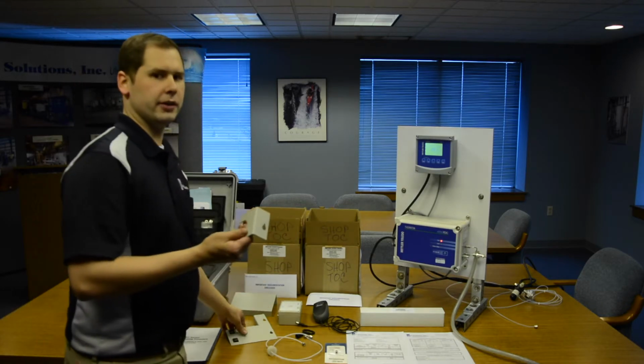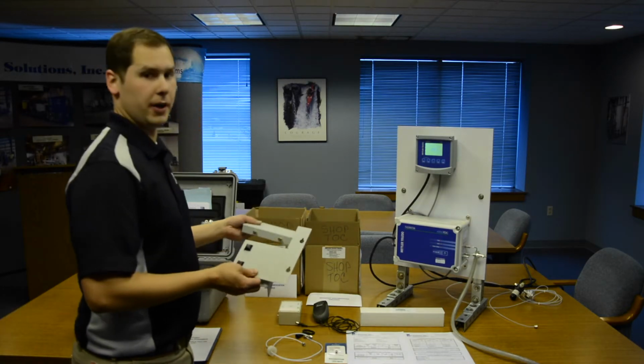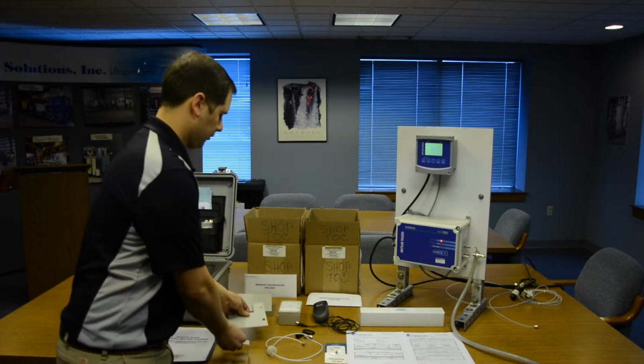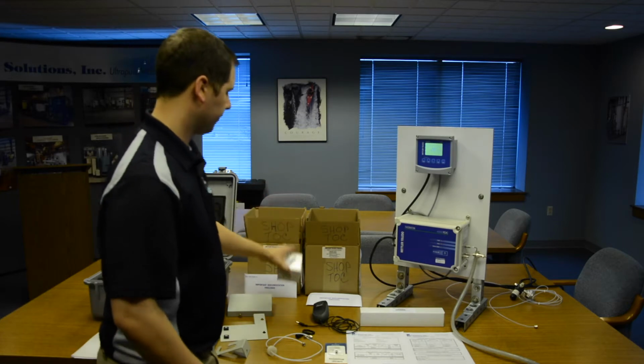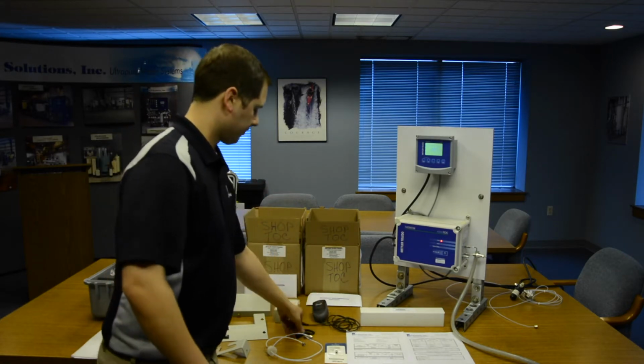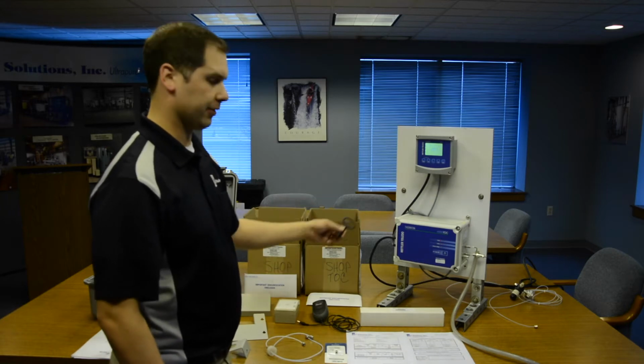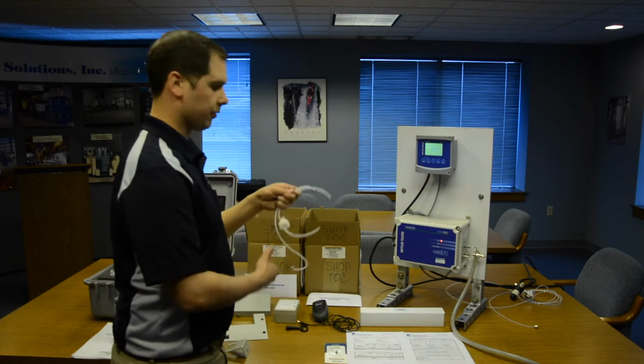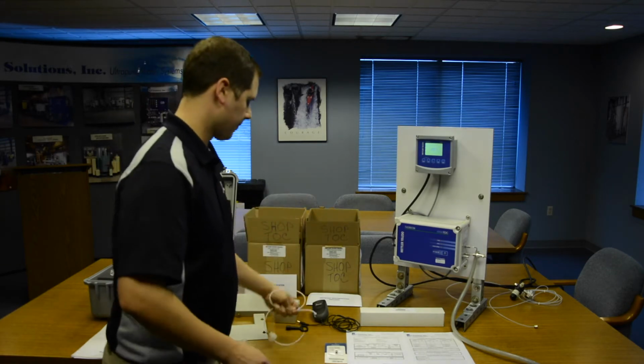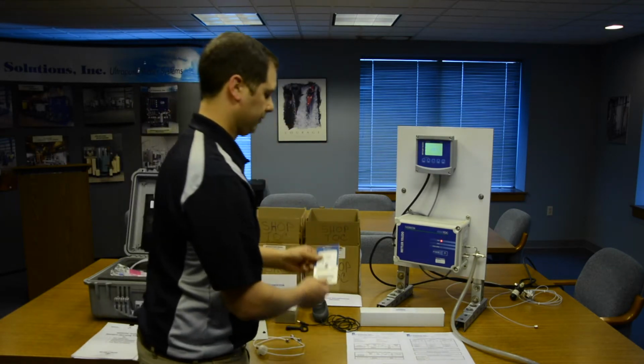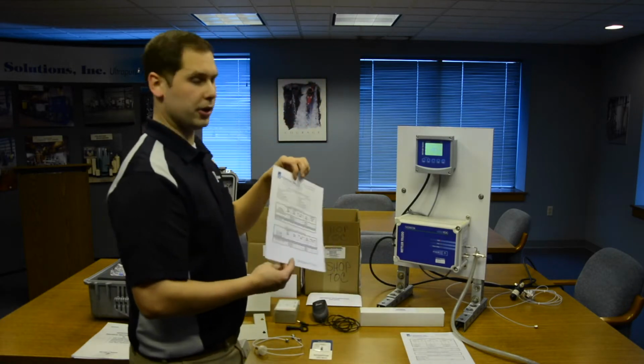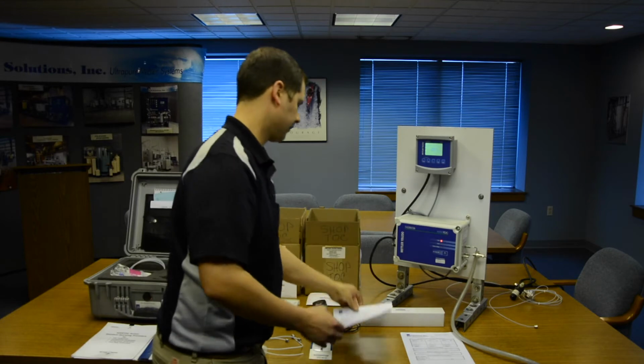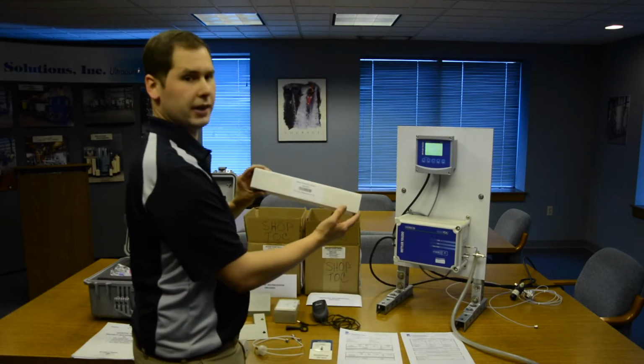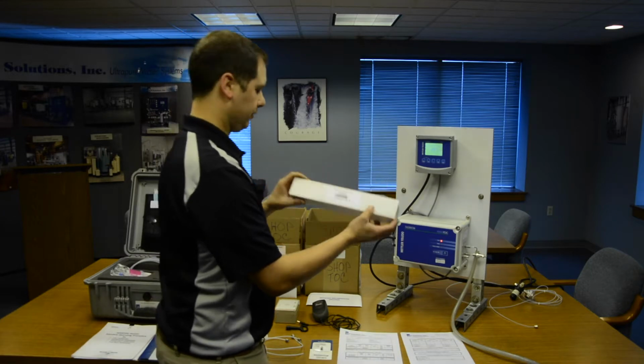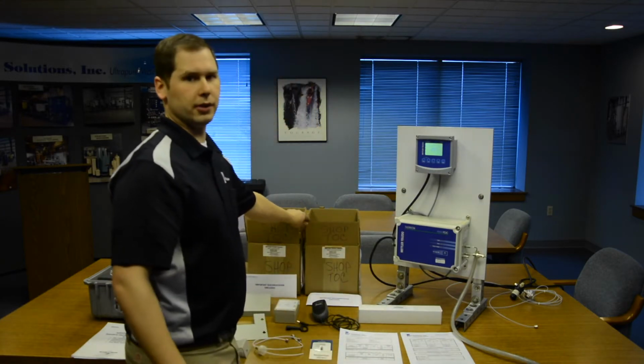You'll need all the hardware necessary for mounting the injection pump. You'll need the injection pump itself, the power adapter for that. You'll need the key to open up the 4000 TOC unit. You also need the connectors for the pump, a new filter, and the calibration and suitability sheet, the UV lamp replacement kit from Toledo Thornton, and the Thornton Toledo calibration solutions.